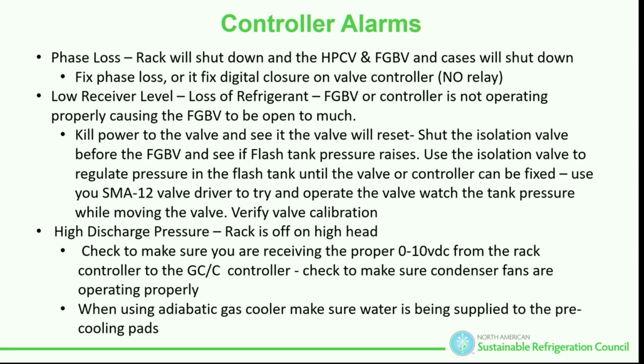When I walk up to a rack, working or not, one of the first things I look at is what my receiver pressure is, because that tells me some things. I need to make sure it's operating. If I'm operating higher than I should be, is that a cause for concern? It's worth an investigation, yes? I always look at ourselves like cops, right? We're investigating a crime. And the way we treat our compressors is a crime, by the way. I'm just saying. All right.